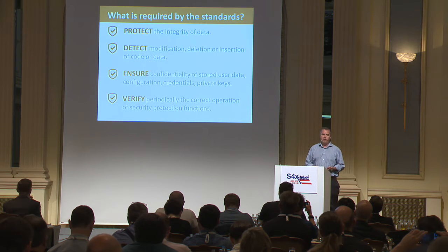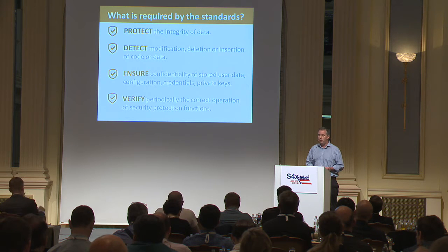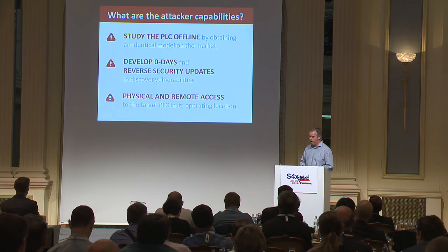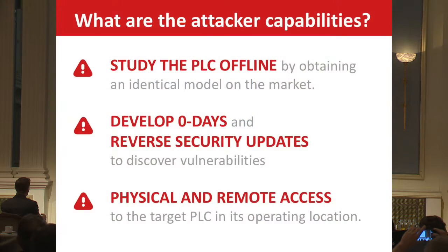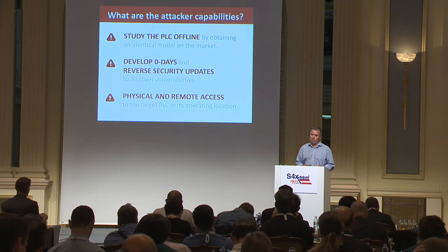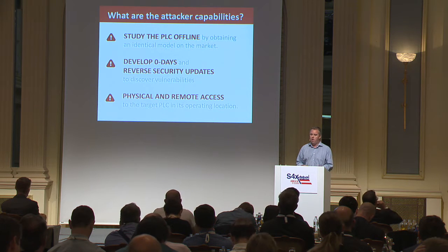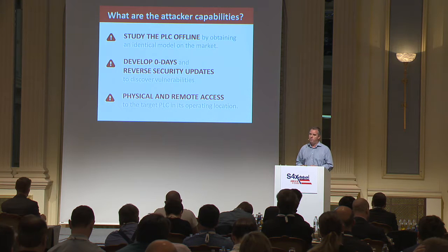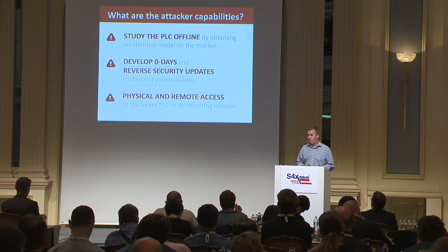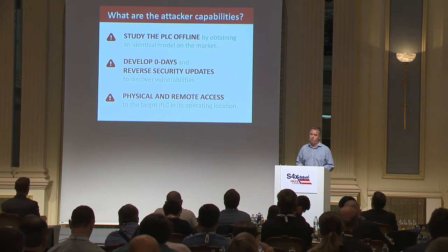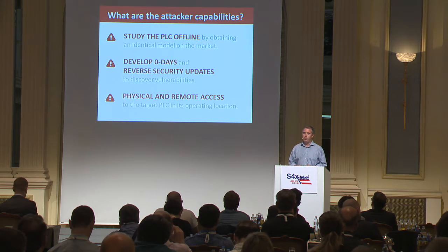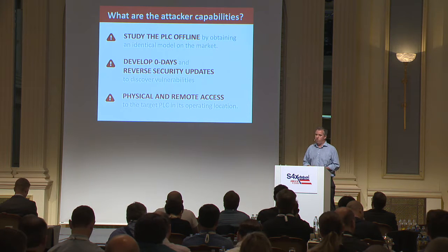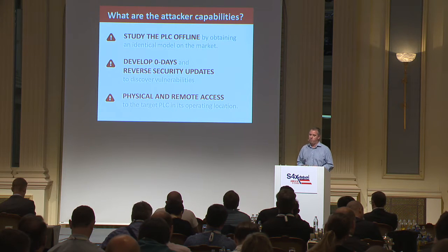In addition to 62443, we have national standards in different countries. In France, ANSSI publishes protection targets for PLCs, and they're explicit about attacker capabilities. They note that we have to assume the attacker can obtain an equivalent device — not the user's device, so it doesn't have the user's secret keys or program, but it is an equivalent device. With that device, the attacker can spend as much time as he wants to find zero-days or reverse security updates. It's also explicit that we cannot assume the device is deployed in a physically secure way; we have to assume the attacker can physically access the device.